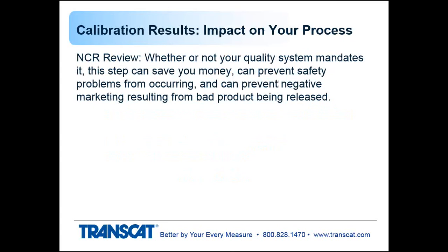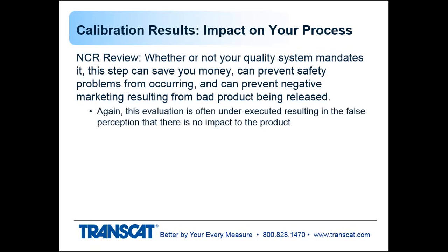So going back to impact of your processes, the cal results, if there's an out of tolerance that flags that you need to do something else with that data now to determine whether there's an impact in your quality system. It can save money by preventing safety problems from occurring and prevent negative marketing results from bad product being released. So the NCR review is very critical for that reason. And it's the whole point of the traceability chain. The NCR review is often under-executed in my experience from what I've seen across a number of companies that I've done internal audits and reviews. And it gives the false perception there's no impact to the product.